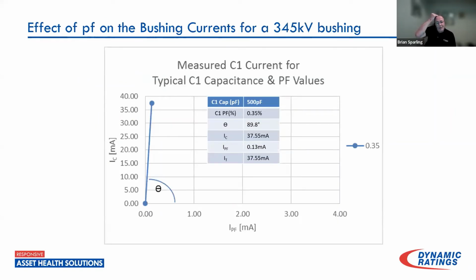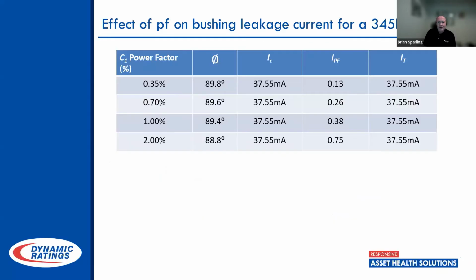So what's the effect of dissipation factor, power factor on the bushing currents? And this is of a 345 kV bushing. So what we're seeing here on the scale on the left-hand side is the leakage current being measured. And as the phase angle changes, you can see the C1 number changes as well. So the phase angle is indicative of a dissipation factor problem inside the bushing. As the phase angle continues to change, the leakage current is increasing over time. So this is how we determine how dissipation factor changes from a capacitance change in the bushing current itself. So over time, as the power factor changes, the leakage current IPF changes over time as well.